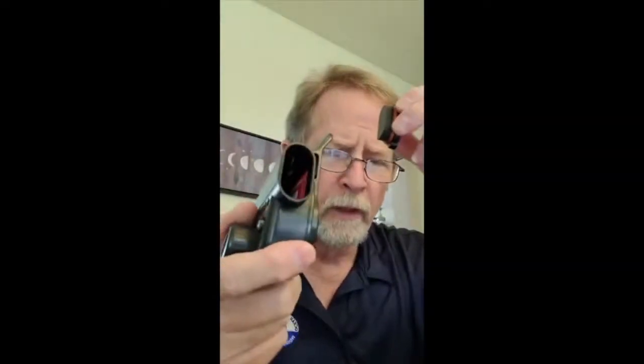A lot of people ask, why is this cap like this? Why don't we put screws on it? This cap is basically a sacrificial cap. If you have a hair, fiber, or something that interrupts or breaks the seal of the O-ring to the battery cap, what happens when seawater mixes with the battery is it builds up pressure on the inside. If there's no means for that pressure to go away, there's potential for cracking the housing. So this sacrificial cap will blow off, you'll flood it with salt water, and lose your battery and most likely the cap.